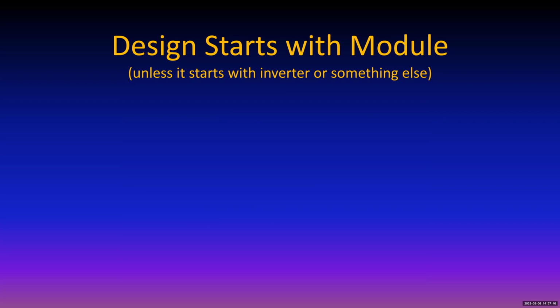Usually the design starts with the module, unless it starts with something else. That may sound crazy, but it is possible to do these things every other which way, and it's generally an iterative process before you end up with the final result anyway. So a lot of times the way you start is you simply figure out how many modules you want to put on your roof, or see if you can fill your roof with modules to the extent allowed, or maybe you have a favorite inverter that you want to use, or favorite microinverters, or whatever the reason might be.